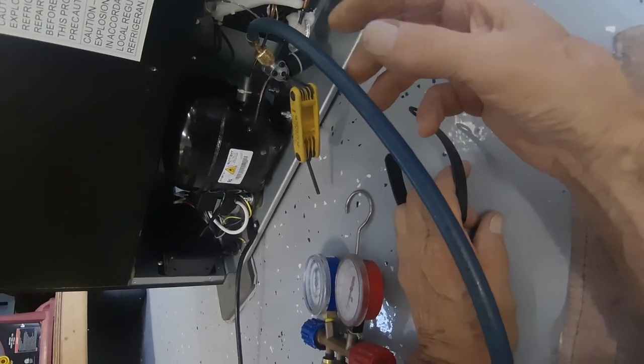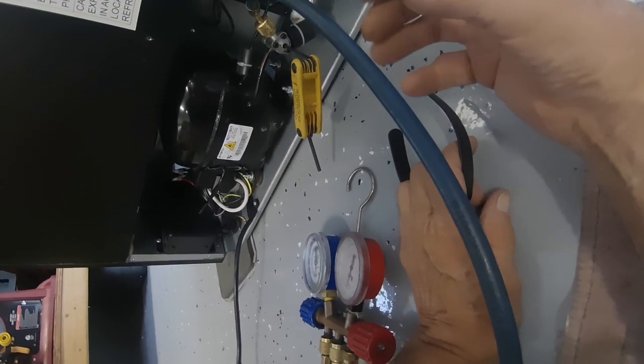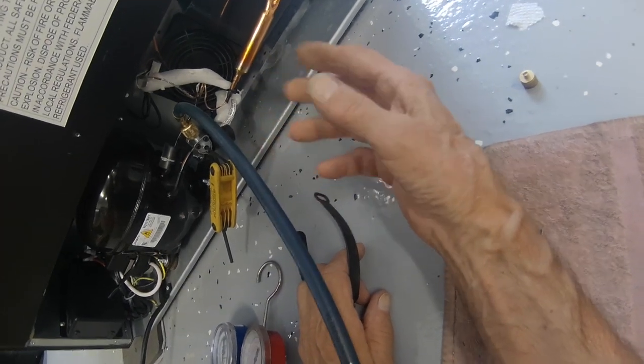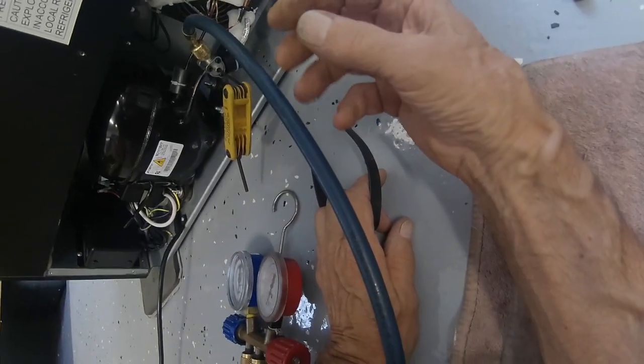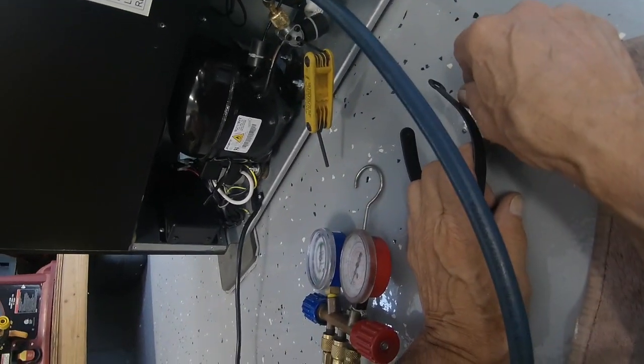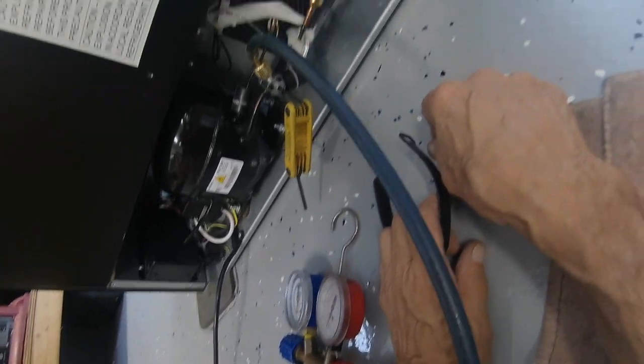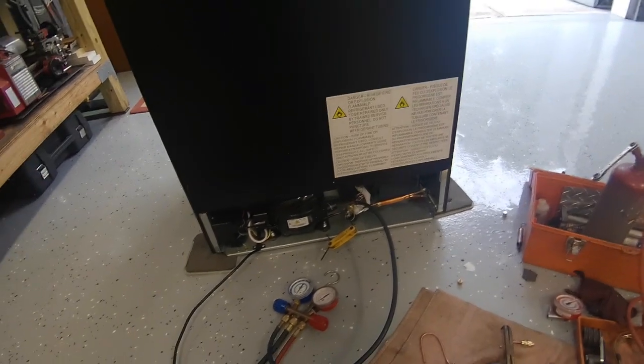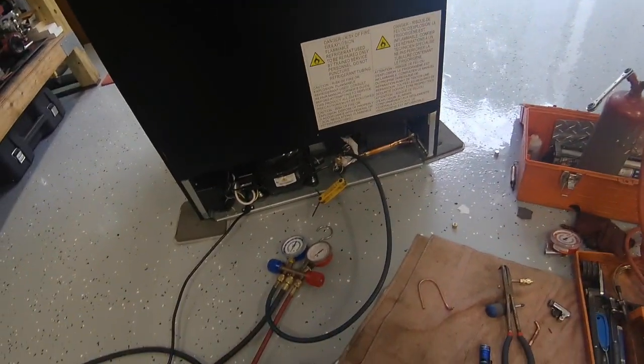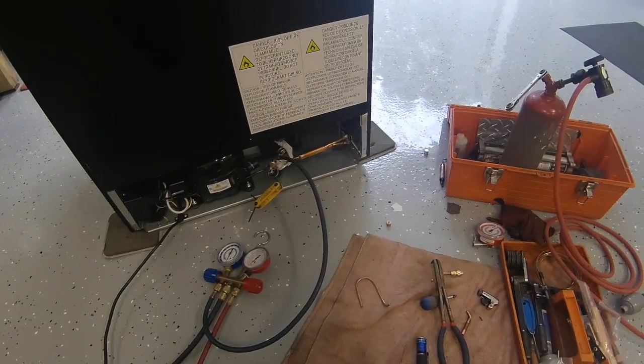You know what? I know on a Sub-Zero, when they're low on Freon, you can hear the Freon running through the evaporator - it makes this gurgling noise. That's what I hear when it's low on refrigerant. So let's let it run and see if maybe it's pulling anything out of there, but it's got to be completely empty before we put any refrigerant in.